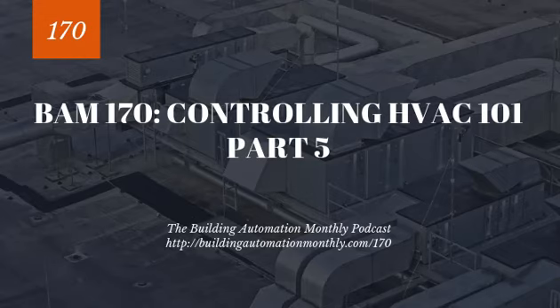Now, what's going on with variable volume pumps is that you are going to vary the flow based on the demands of that primary loop. So you're going to increase flow as needed. But with a constant volume pump, it's going to be sized directly to that chiller, okay? So the big difference in controlling this is that with just static, constant volume pumps, you are not going to be able to do much with your GPM, and you're going to really have to focus, if you have a secondary loop, on getting that secondary loop control tight.